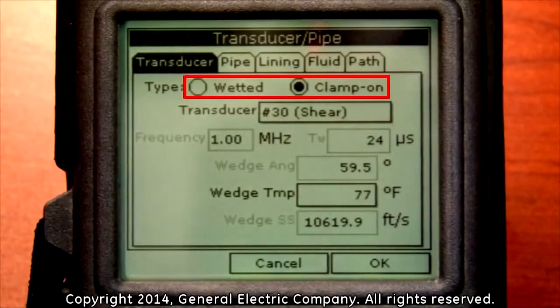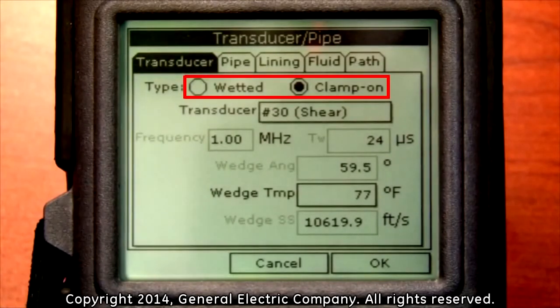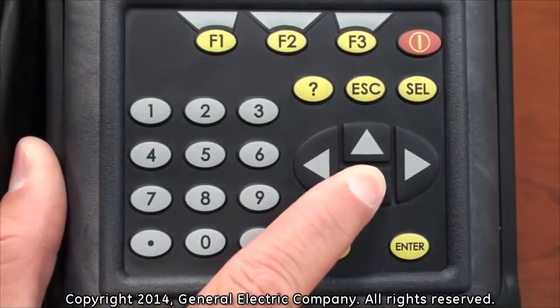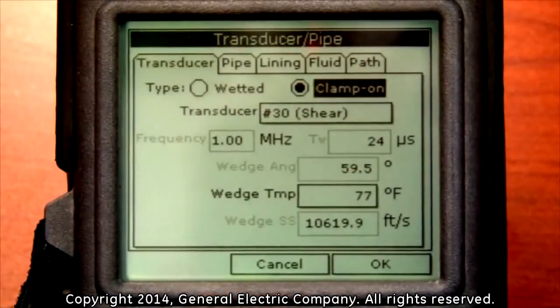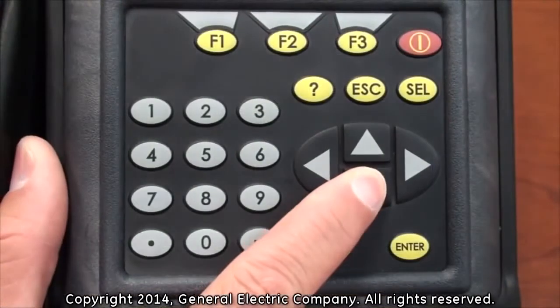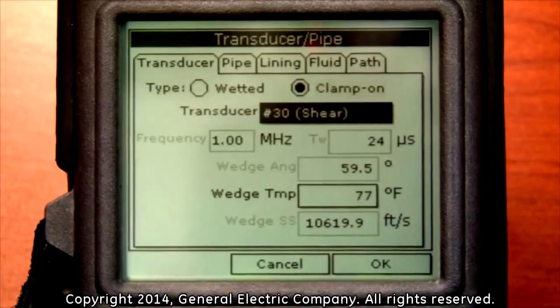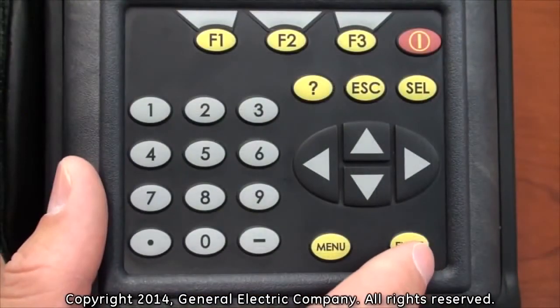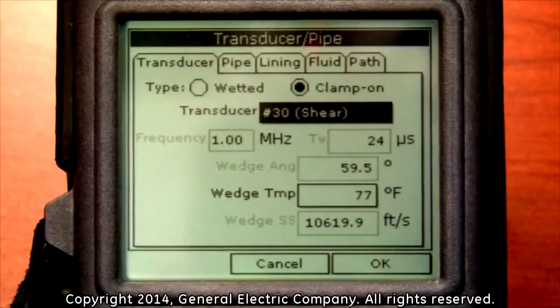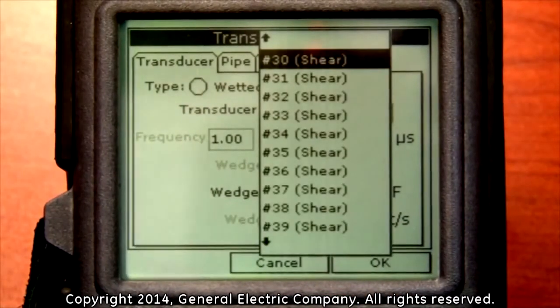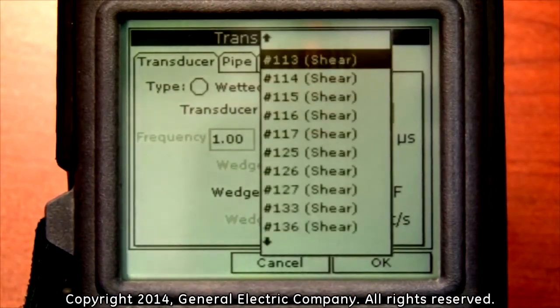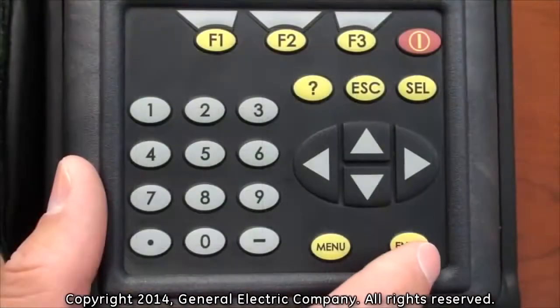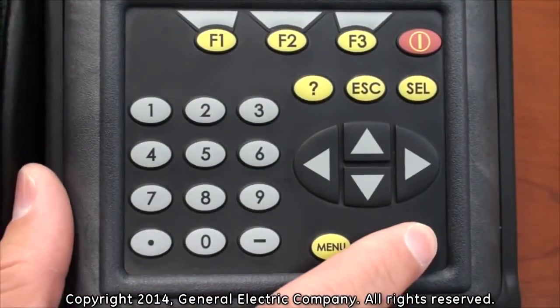In the type options, you can select either wetted or clamp-on. Press the down arrow key on the keypad and then the left or right arrow key to highlight either of these types. For this example, we will use the clamp-on option. Once you have selected your type, use the down arrow key on the keypad to highlight the transducer option. Press the Enter button in the transducer selection block and you will see a list of transducer types available for selection. Highlight the appropriate transducer type you are working with and press the Enter button to use the selection.